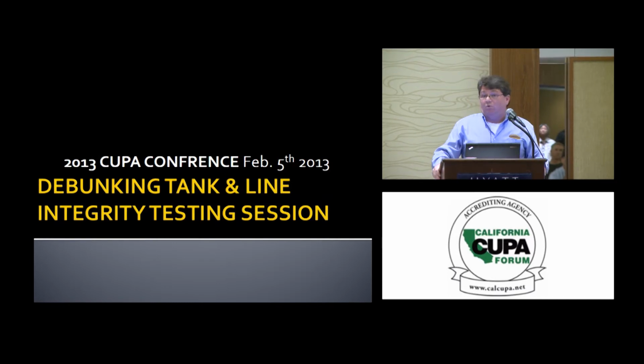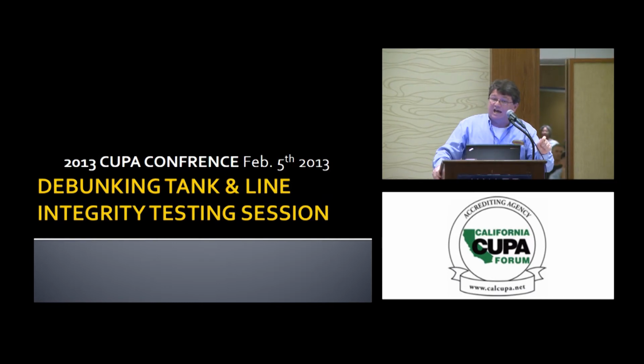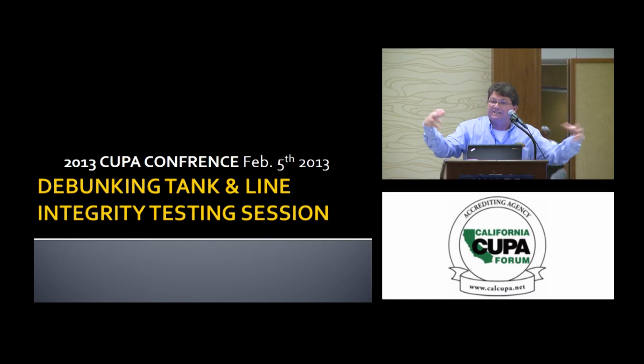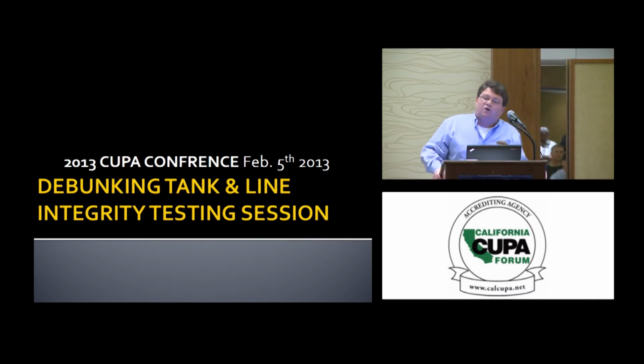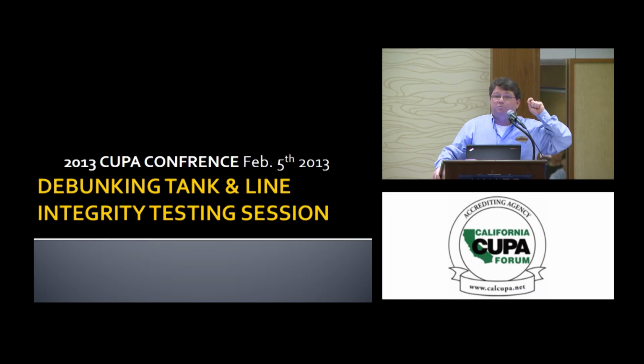Water is an issue everywhere. It's getting into the gasoline and it's pulling issues out. See, MTBE would get out in the environment, be a problem. Now water gets in. So now we're trying to protect everything from the water coming in on ethanol-based products, which means tank tops. Tank tops, tank tops. Now, 40 CFR Subpart CCCCCC is not applicable to you. However, testing a Stage 1 tank top is the most important test with an ethanol-based product.